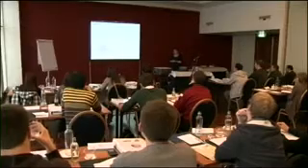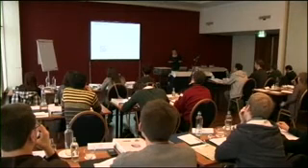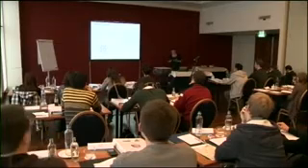And in fact, Professor Rietveld came up with this idea in the 1950s. The problem at the time was that there were no computers available, so when you have about 10 phases and in each phase you have maybe 100 atoms, it's just impossible to make the calculation. But now we have computers, so with this large number of phases and atomic positions, we can make these calculations in a matter of seconds, and it's quite easy to iterate these two together to find out how much of each individual phase is present in the mixture.